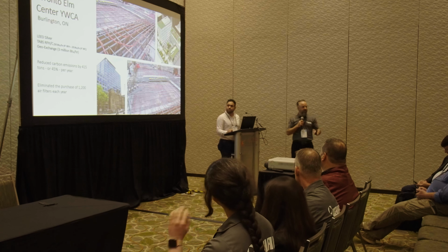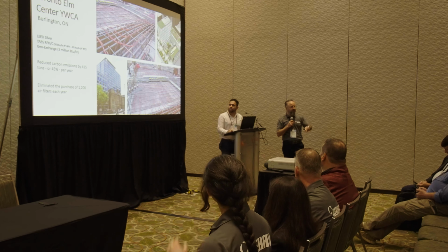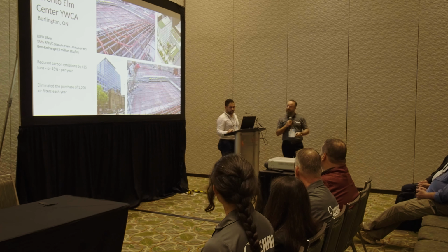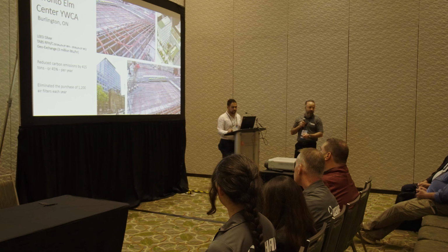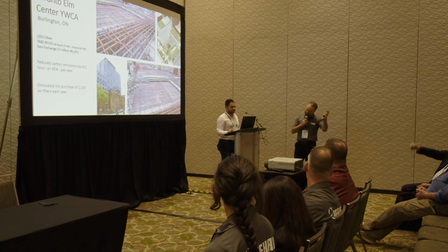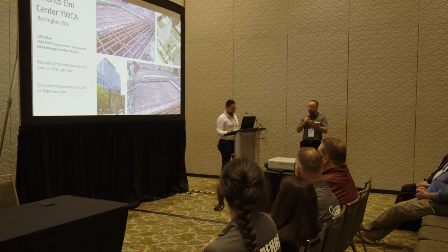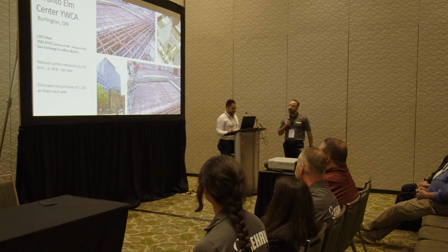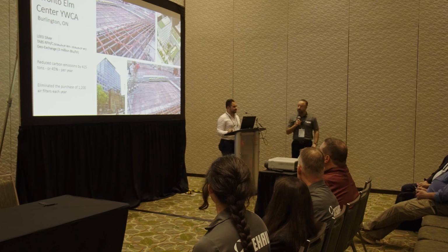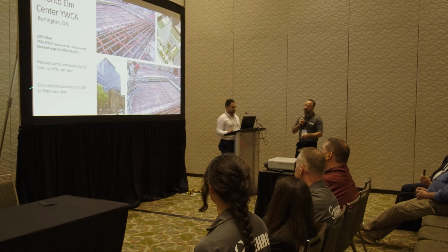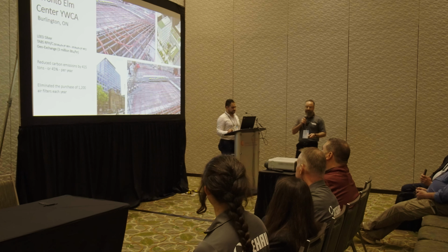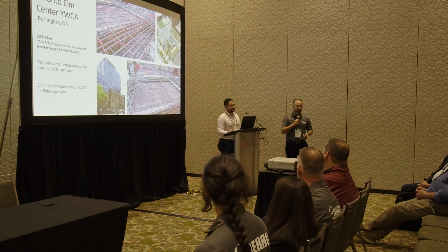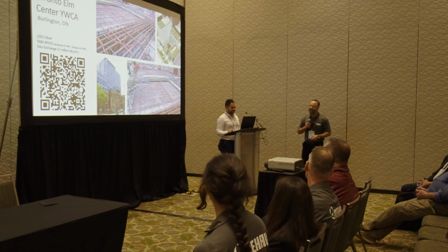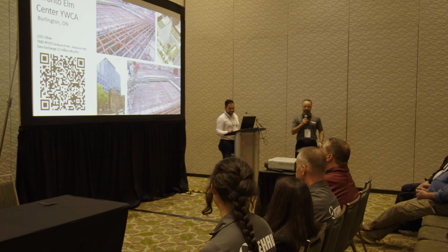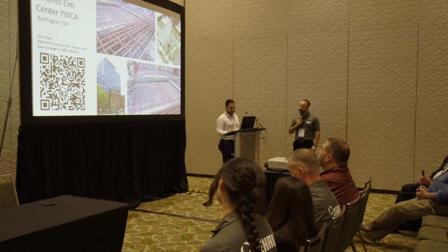They have 90 geothermal wells underneath the parking, each 150 meters, and they're delivering 3 million BTU per hour. How's that? You are an expert, okay. And with the whole project, we were able to achieve a 45% reduction in carbon emission, which is a big deal. And since we were able to downsize the air system, it eliminated the purchase of 1,200 air filters per year, which the maintenance guys love. Again, if you want more information, please scan this barcode, and it takes you to the page.